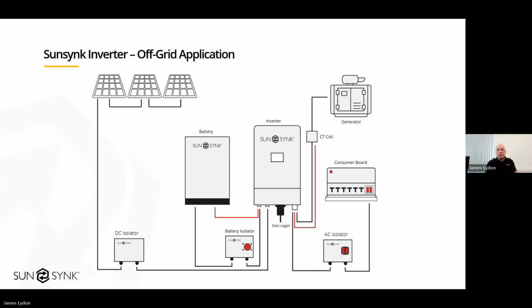Off-grid. So we've got the backup generator on this one. The generator input on all of our inverters can do 3 things, but only one of them at once. So if someone wants to AC couple into our inverter, you can do it the way I mentioned earlier, leaving the grid-tied system exactly how it is, and just with the CT clamps, we can see when it's exporting. The other way of AC coupling is you can chop the AC feed to that existing grid-tied string inverter and connect it straight into our inverter. And then all the power will pass through us.